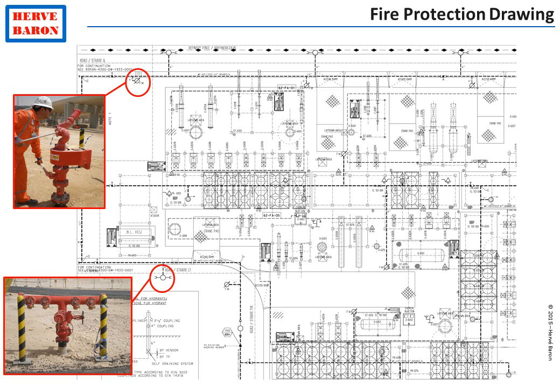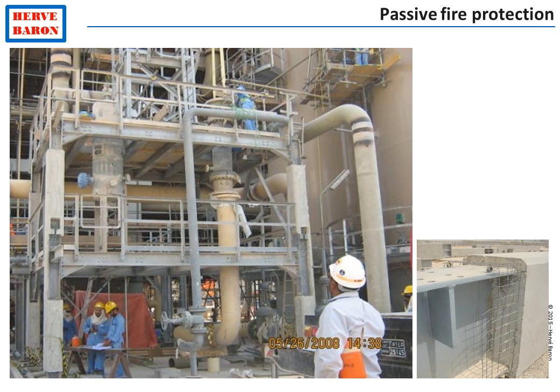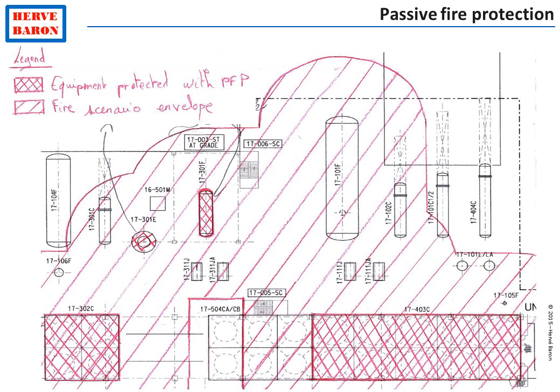Fire protection also includes passive fire protection. Passive fire protection consists of a coating applied to equipment supports, process structures, or pipe racks — with concrete for an onshore plant, or a special type of coating for an offshore facility due to weight reasons. To identify which equipment shall be protected with passive fire protection on their supports, safety draws the likely fire envelope and then identifies within this envelope the equipment which have a significant flammable product inventory.